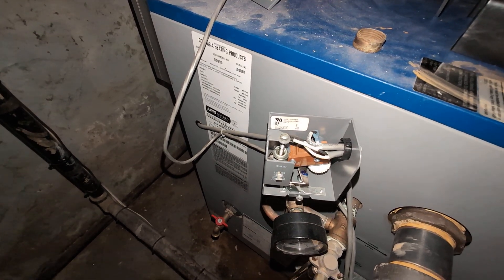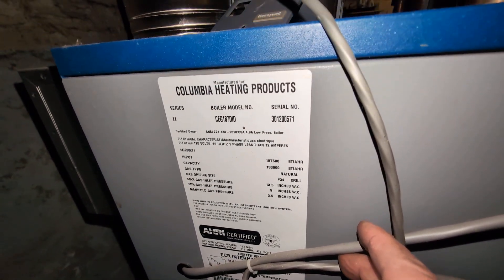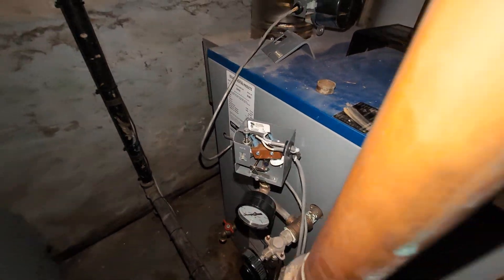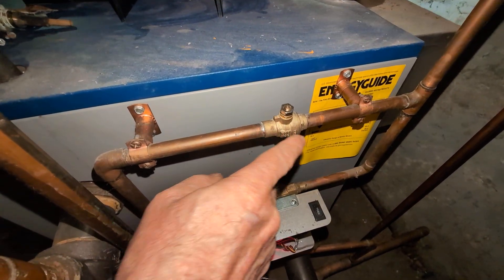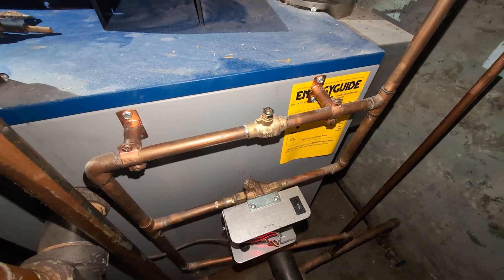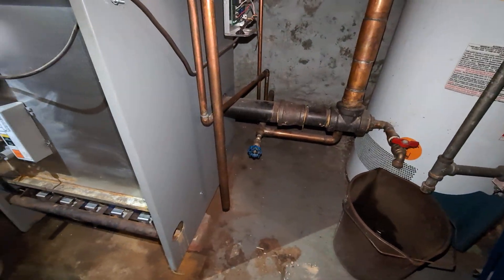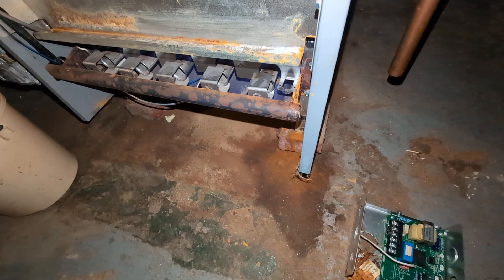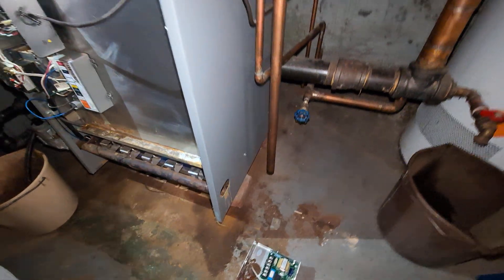Good day and welcome to my channel. What we have here is a Columbia Heating Products CEG boiler, 187,000 BTUs. One of the major issues we've had over the years is a flooding problem. We think this valve here is probably passing water. When the system flooded last time, the customer noticed water on the floor — and having water on the floor when a boiler floods is concerning, as it could be evidence of a failing boiler.